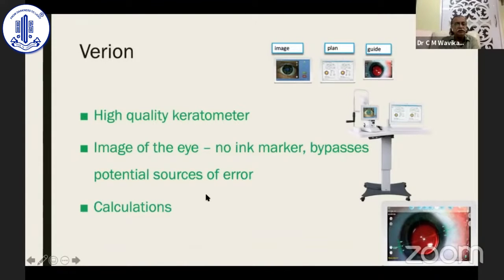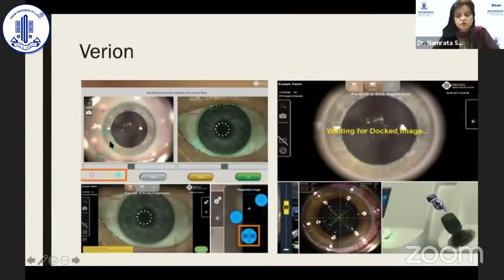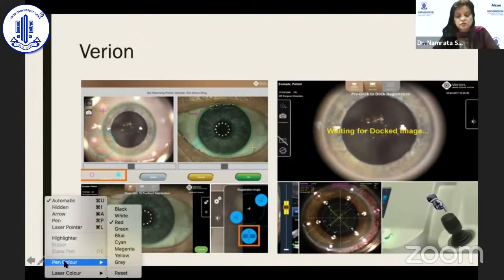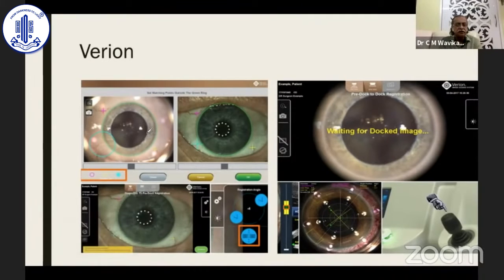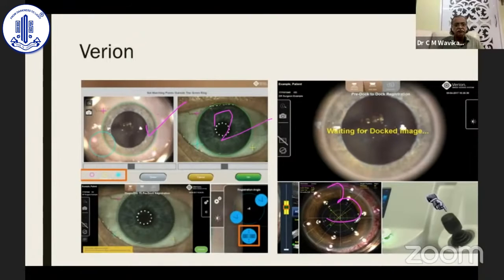Because of registration, you don't require an ink marker, and it also bypasses many potential sources of error like head tilt and cyclotorsion. It also does calculations for us and increases the accuracy of placement of the lens in the eye. Diagram one is taken in the OPD. Diagram two is taken pre-docking with the lens. Diagram three is taken after docking or post-docking. Diagram one is matched with two, and two is matched with three, and therefore one is matched with three to complete the registration process. This sounds very difficult but in reality it is very simple.